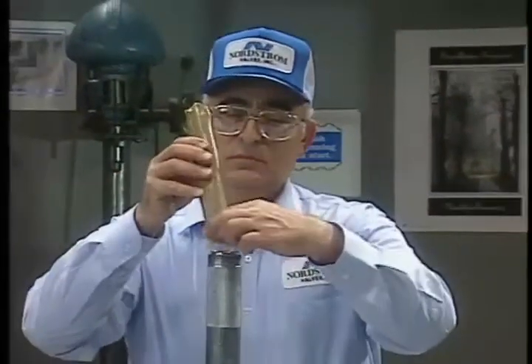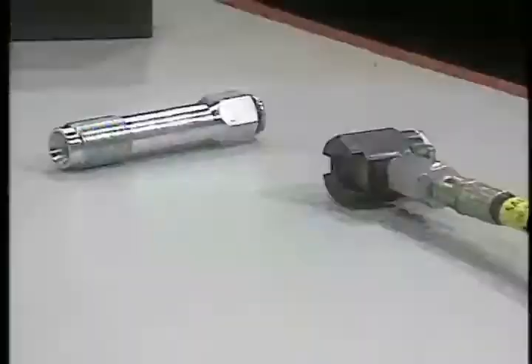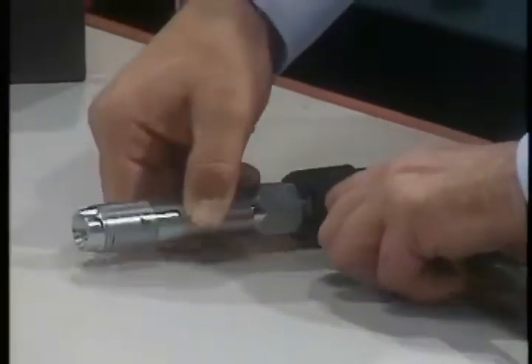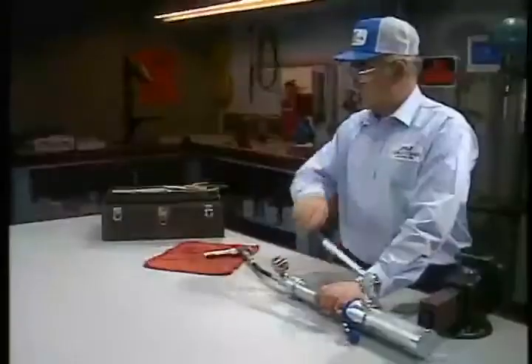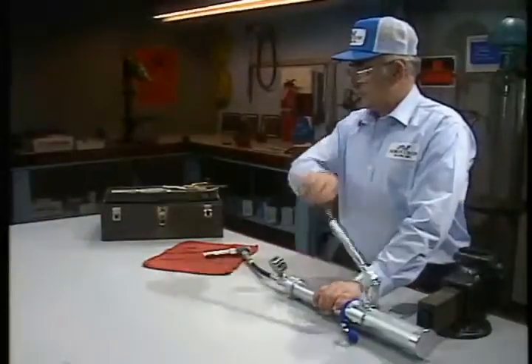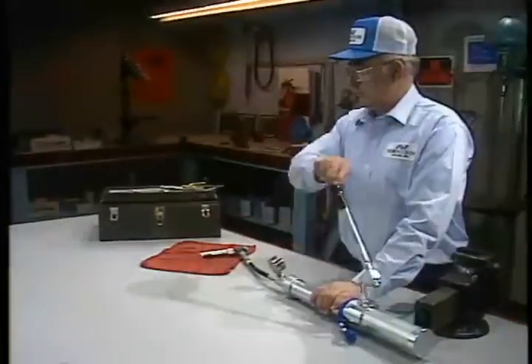To purge the system, load the sealant you want to use into the handgun. Remove the giant button head coupler from the hose, or slide a spare sealant fitting into the button head coupler. Operate the handgun to pump the old sealant from the end of the hose through the fitting into a container. You can tell when the new sealant appears by watching the stream.